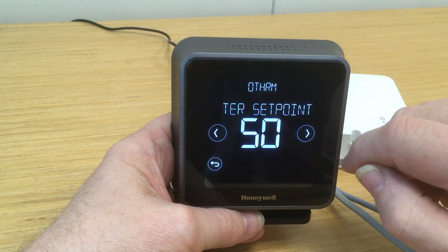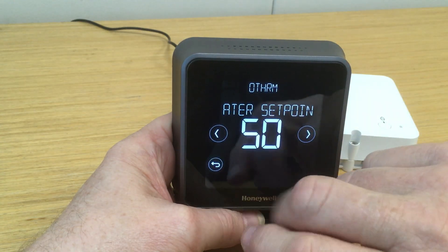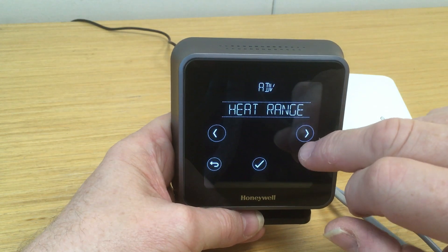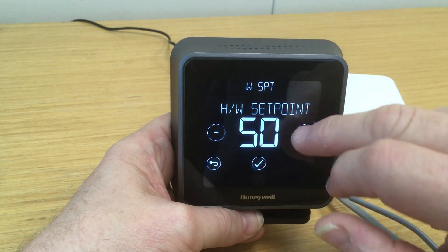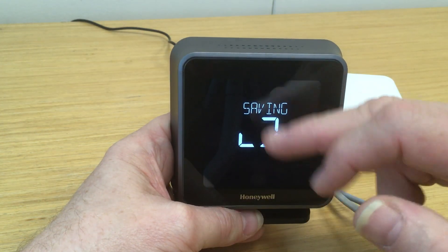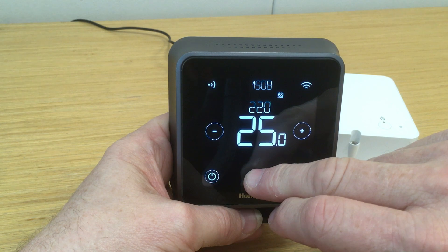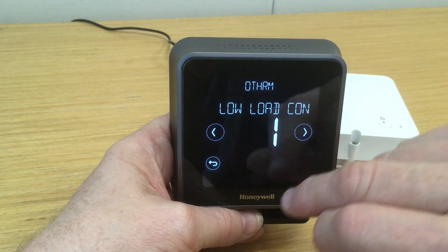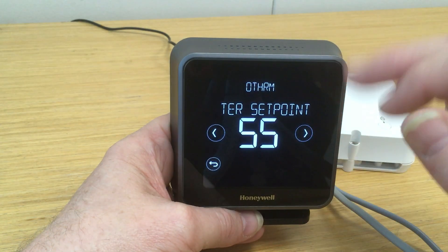And then the next option is the actual hot water set point — we're currently set at 50 degrees. Now if we want to change that, we come out of that menu, go back to the advanced main menu, scroll forward until we get to hot water set point, press the tick, and we can now change that set point. So maybe we want to make that 55 degrees — press the tick, that will now save that reading. We can verify this by going back into the advanced menu, scrolling forward to OpenTherm, then to the hot water set point, and we now have 55 degrees, which is what we set.